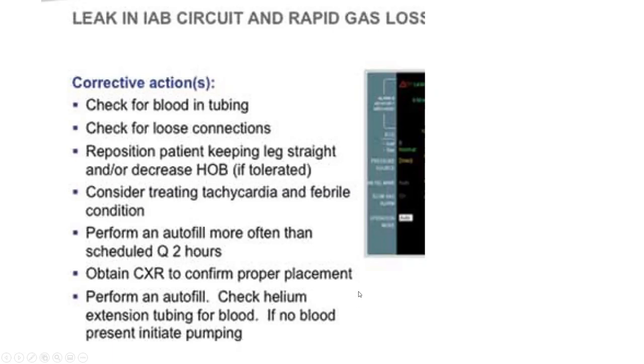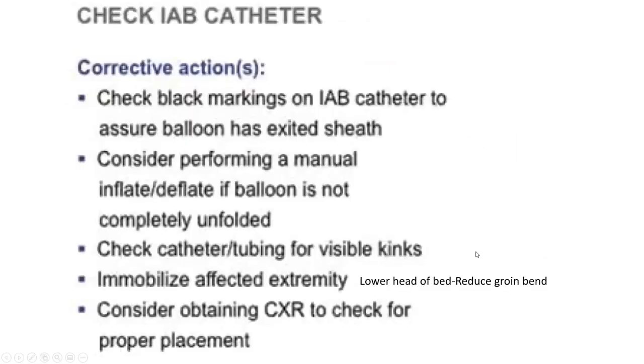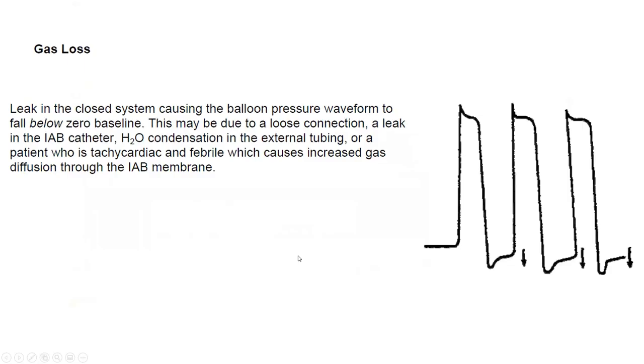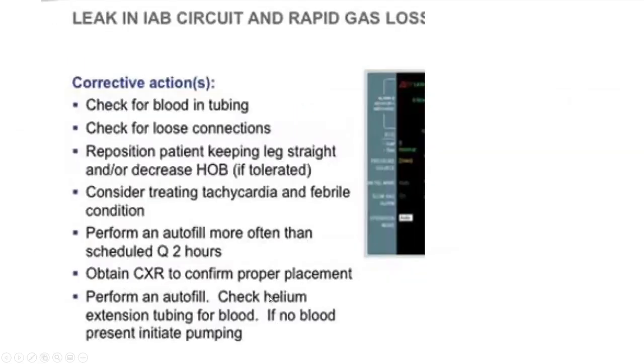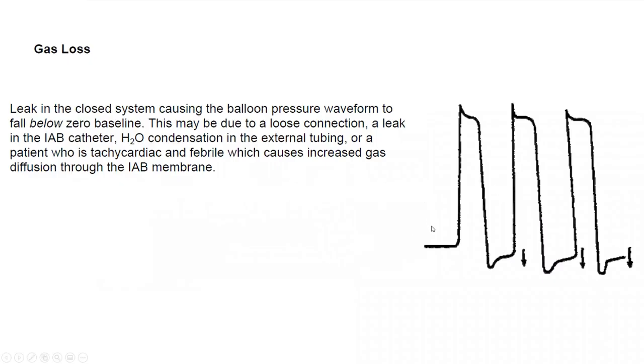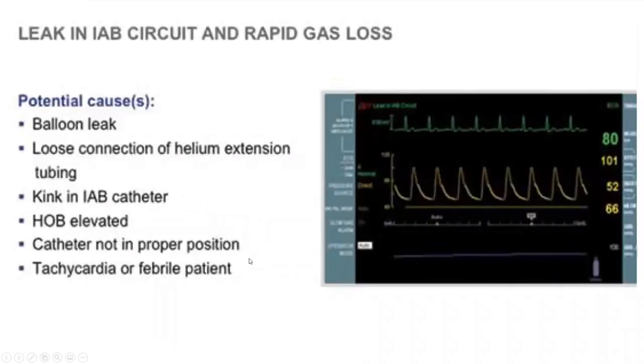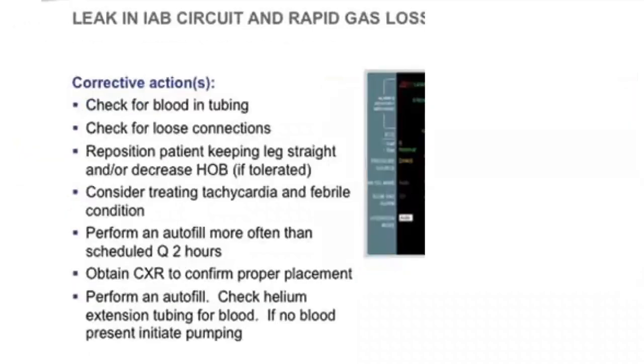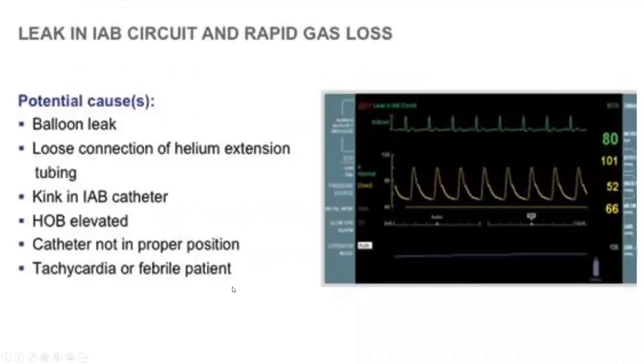Okay. Another thing you can do in those cases, something like that, or even with poor deflation like this, as long as you're sure there is no leak from a balloon rupture, you can do manual inflation and deflation. On occasion, those poor waveforms, whether poor inflation or deflation, could be explained by a balloon that hasn't unfolded well. And so it's not able to expand because of that. And so you do a manual inflation with a 50 cc, 50 milliliter syringe, and deflation, and see if that can create a waveform.